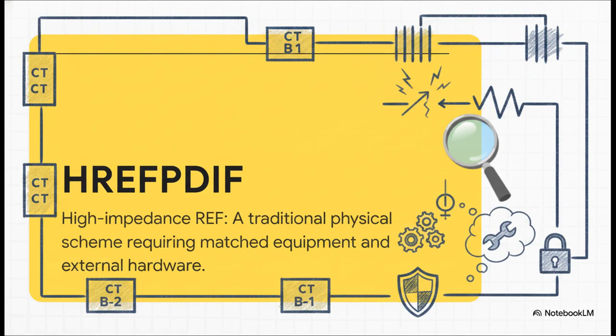On the flip side, we have HREFPDIF, the high impedance REF. This is your old-school traditional method. It relies on a physical high impedance path to provide extreme sensitivity for faults near the neutral point. But that extreme sensitivity comes with some pretty intense hardware constraints. It strictly requires identical CT turns ratios throughout the circuit, and it usually demands external hardware like stabilizing resistors to even function properly. So, it trades that software flexibility for rock-solid physical stability.